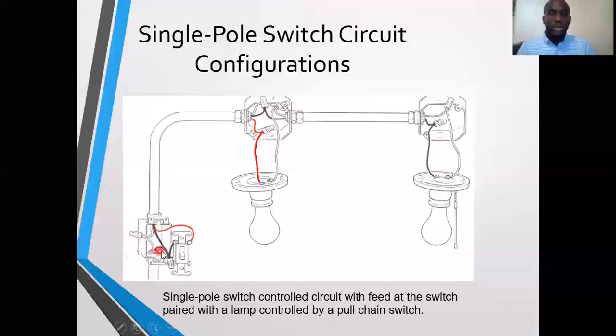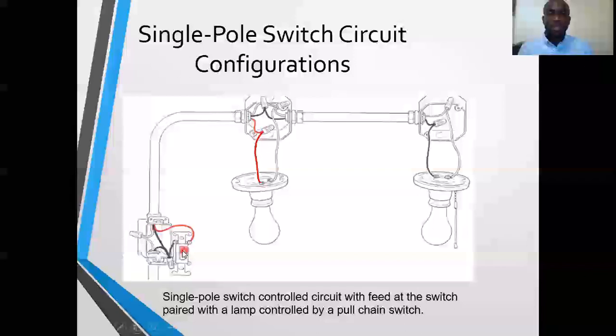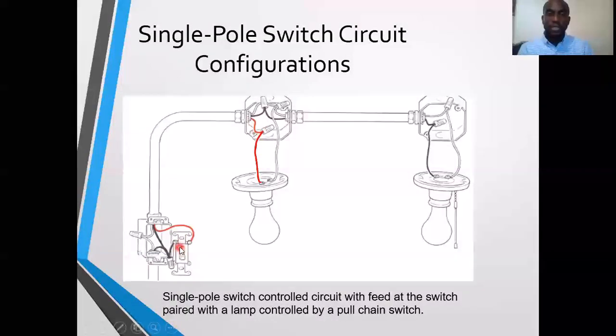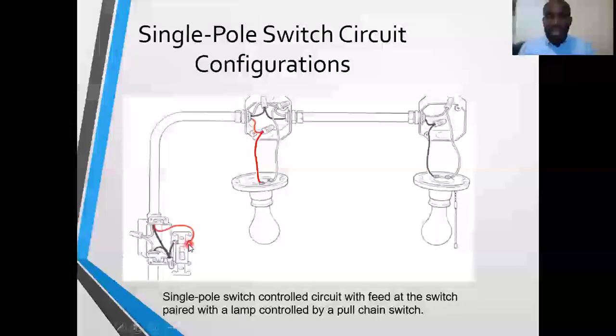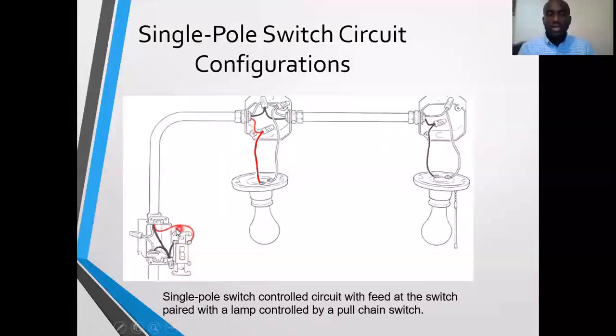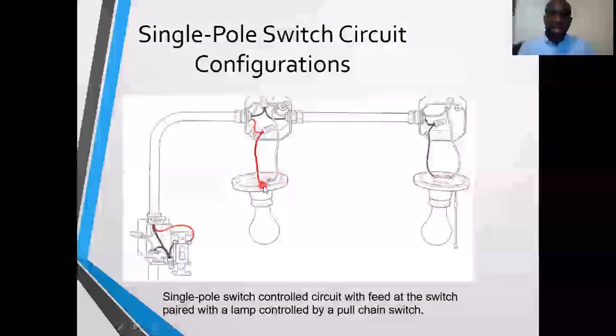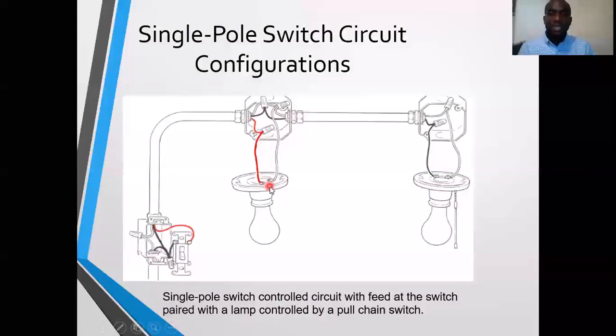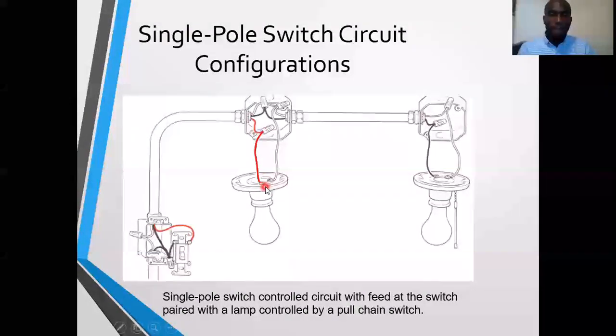So the feed is at the switch. We splice or share the main source hot, send one to this first switch which is the single-pole switch inside the switch box, and then we take from that switch the switch feed, send it all the way to the first keyless. This keyless, we will connect it to the brass or bronze terminal.